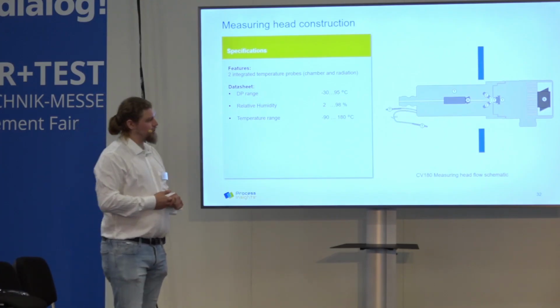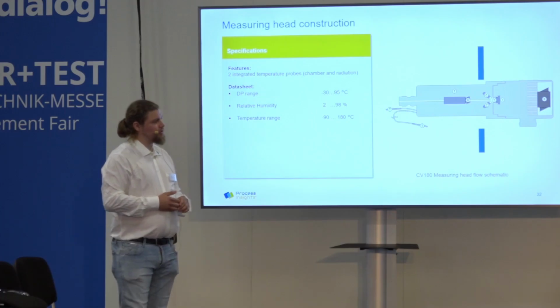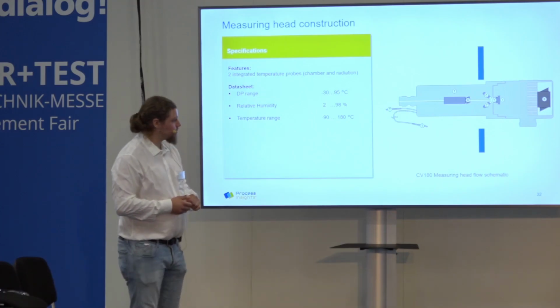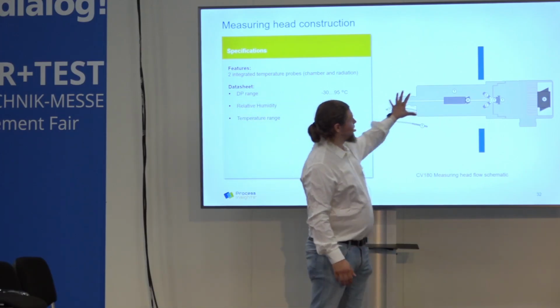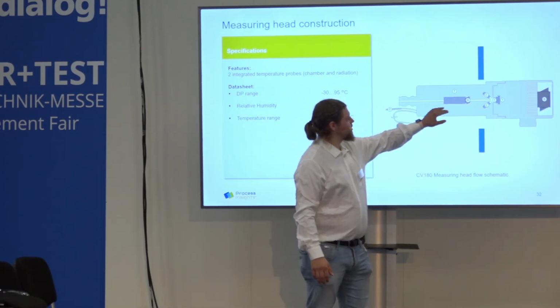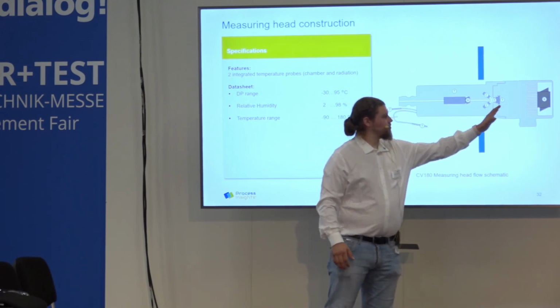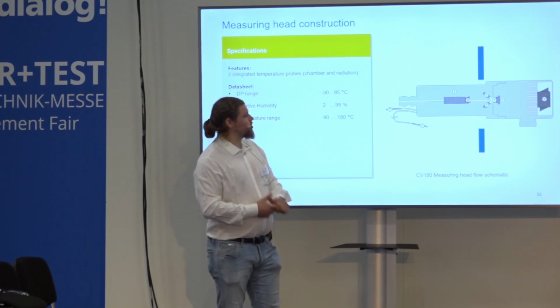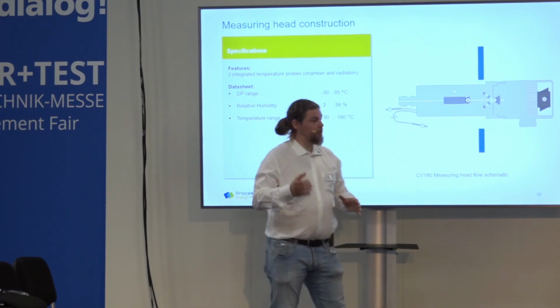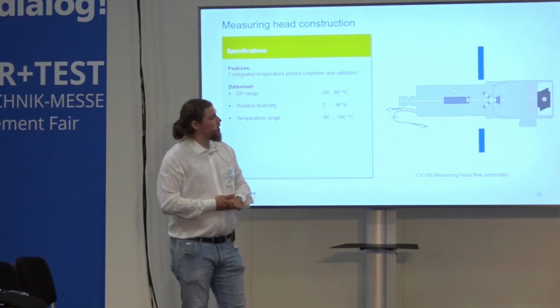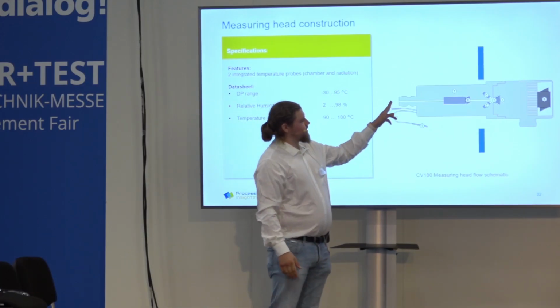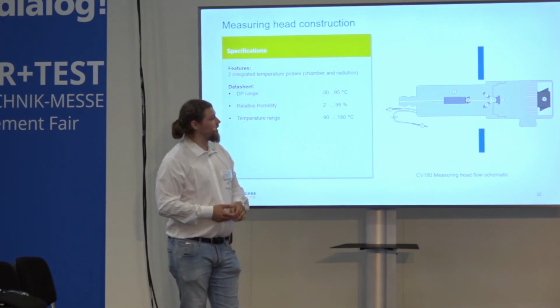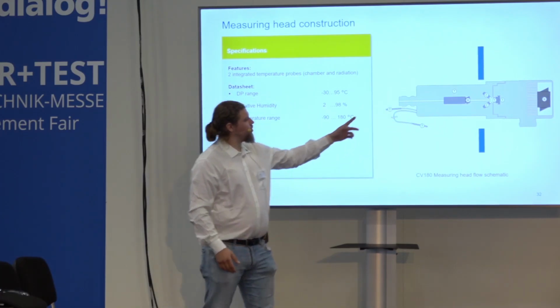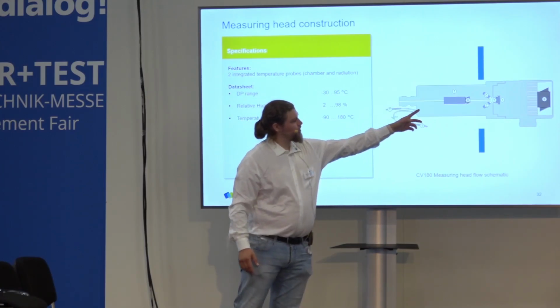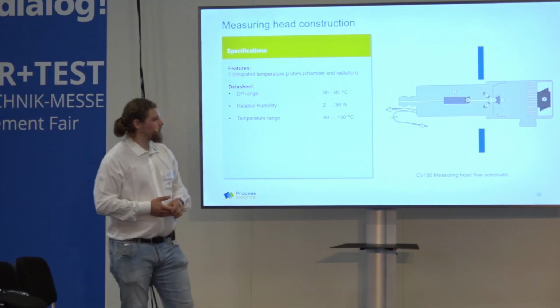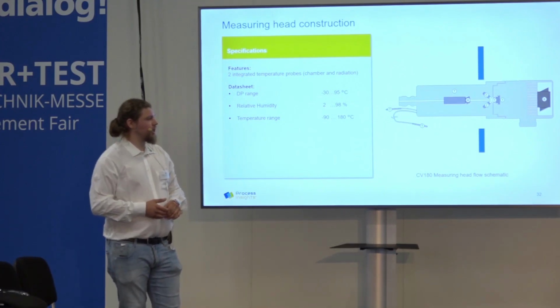So let's first have a look at how the CV180 measuring head looks from inside. Generally, we have, again, these two parts. The first part is the optics. You have the LED and the photodiode, and the second part is the thermal control to have this surface to a certain temperature and to get the dew point temperature reading. And what you need as well is to get the sample from the climate chamber to the mirror. So in the sample path, we have included in the outlet a pump so that the measuring head is able to work.